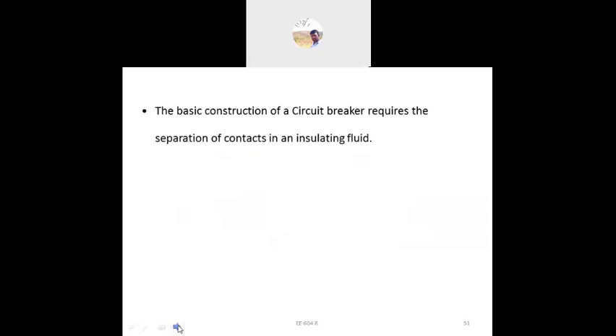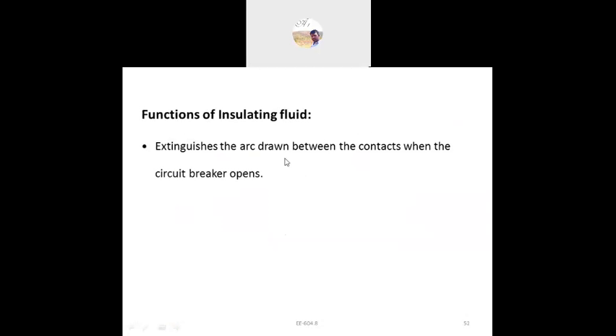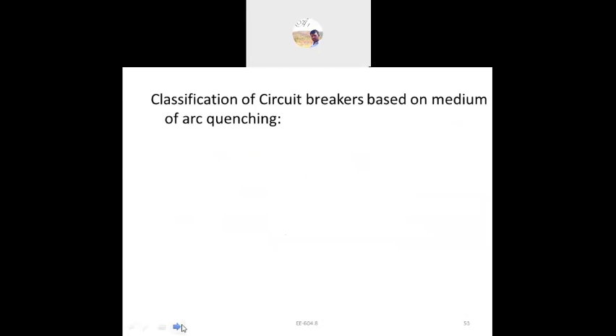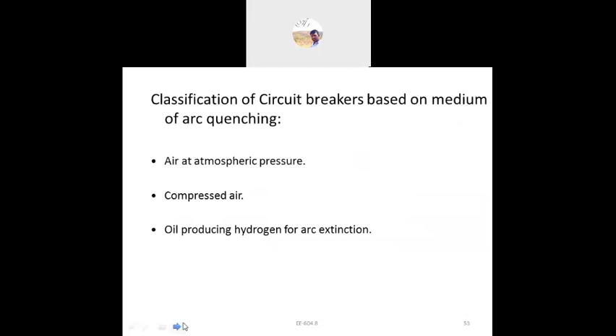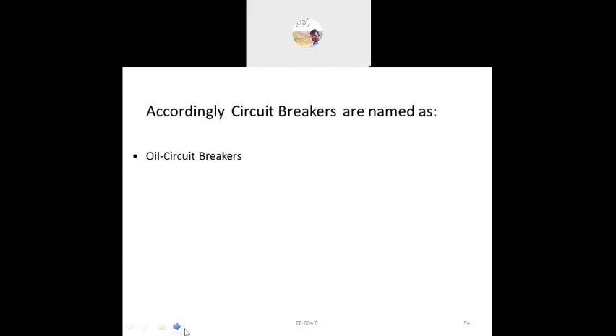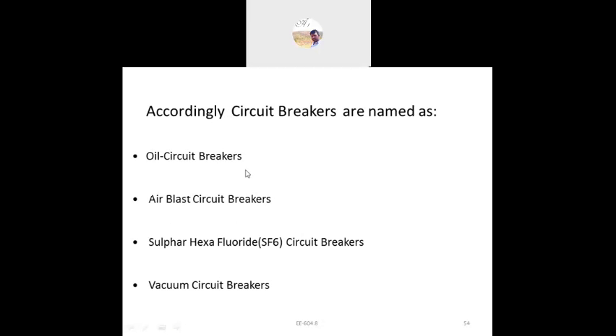Here we see the basic construction. The function of the insulating medium is extinguishing the arc drawn between the two contacts when the circuit breaker is open. It also provides insulation between the contacts and from each contact to earth. This is based on arc quenching, and the quenching mediums are air at atmospheric pressure, compressed air, oil producing hydrogen, and ultra high vacuum and SF6 gas. According to the medium, we have the oil circuit breaker, air blast circuit breaker, sulfur hexafluoride circuit breaker and vacuum circuit breaker.